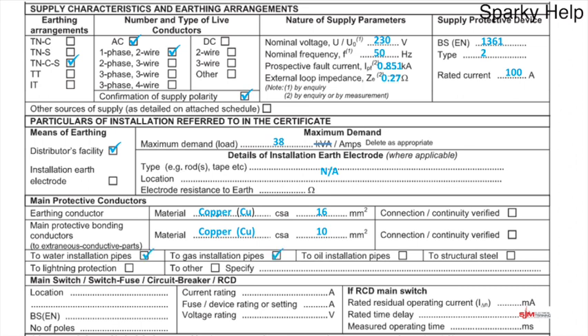Now, if we did a Ze, it means we must have verified its connection, because if we didn't get a Ze reading, then you would not have had a connection, and that would prove that one to be wrong. We're going to assume that main protective bonding has been done. I'm going to get around to doing a video on that, but basically what you'd look to do is remove the main bond conductor from the MET, and do a long lead test from there to the pipework, or whatever extraneous conductive part you happen to be bonding, and we'll tick it because it's your first dead test that you tend to put in, so we'll tick that one.